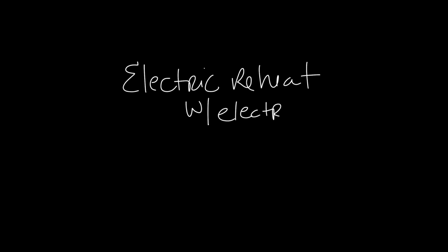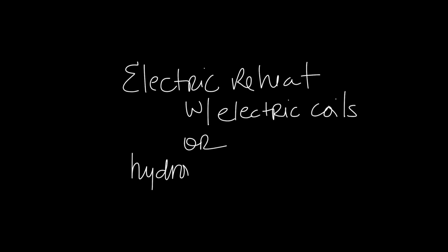The industry standard for an air reheat at the terminal unit is either electric reheat with electric coils or hydronic water coils in which hot water passes through. The Titus terminal unit application team answers many calls on what an appropriate gallon per minute or GPM rate would be to use on a hydronic coil.